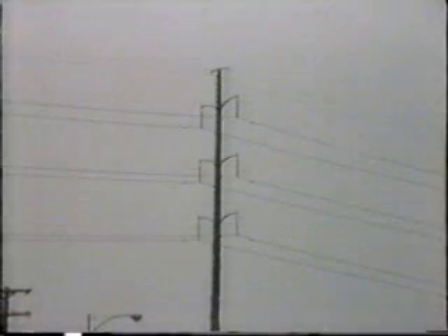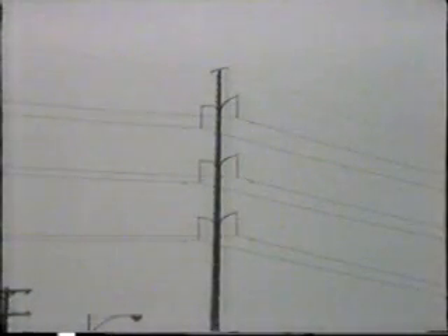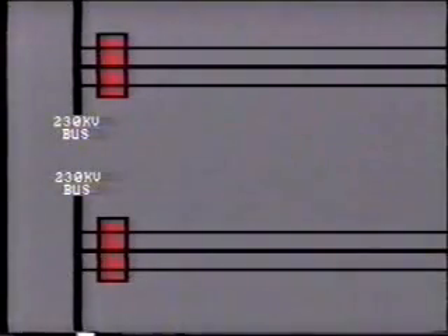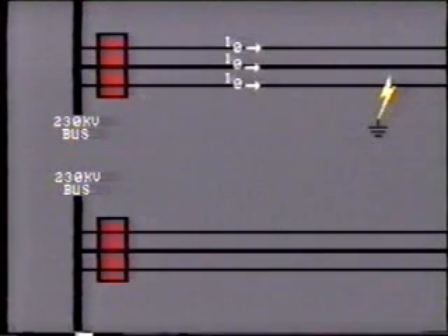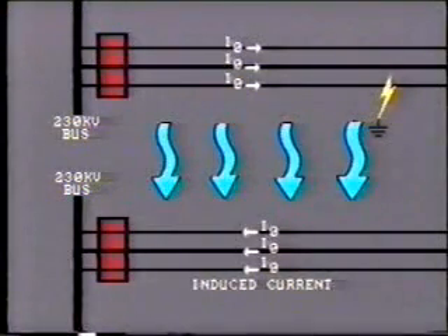Negative sequence components are also used to overcome the problem of mutual inductance. Now, what is this mutual inductance, also called mutual coupling? Well, a typical example would be where we have, say, 2 230 kilovolt lines strung vertically on either side of a single tower. The 2 lines are strung fairly close together, so that there is some magnetic coupling between them. During normal operation with balanced loading, this should not cause any problem, as the inductance tends to cancel out across the phases. However, if a ground fault occurs on one line, then zero sequence current will flow in all 3 lines. These will be of equal magnitude and all at the same phase angle. The result of this imbalance is to induce current into the adjacent line.